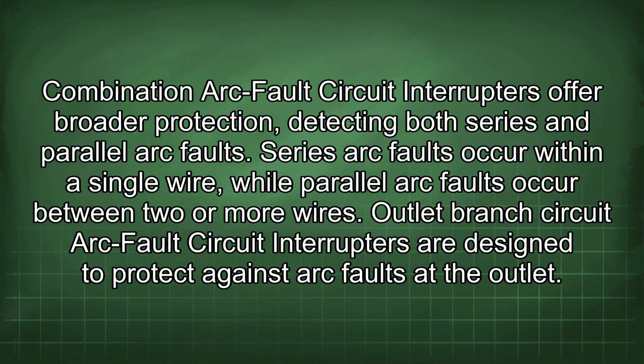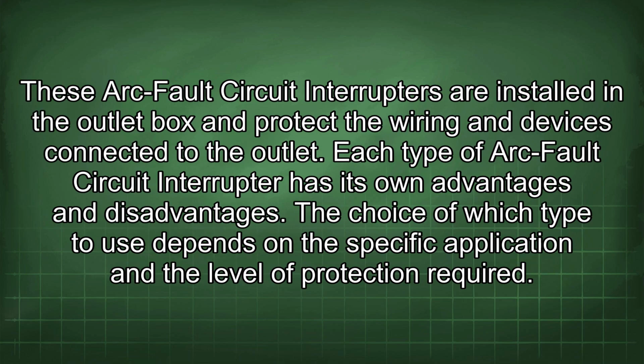Outlet branch circuit arc fault circuit interrupters are designed to protect against arc faults at the outlet. These are installed in the outlet box and protect the wiring and devices connected to the outlet. Each type of arc fault circuit interrupter has its own advantages and disadvantages. The choice of which type to use depends on the specific application and the level of protection required.